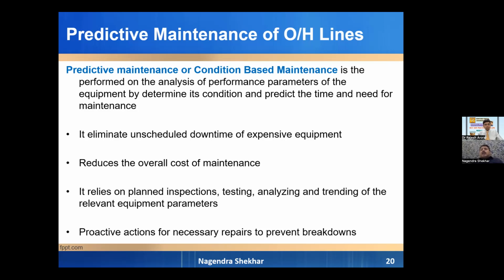But how can we do this condition-based maintenance? We have to continuously inspect our lines. We have to test them and analyze the testing data and trends, to see whether the current leakage is going up or reducing and so on. And proactive action is required for these condition-based maintenances so that our breakdowns can be prevented.